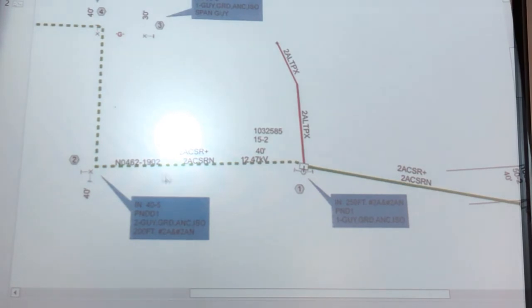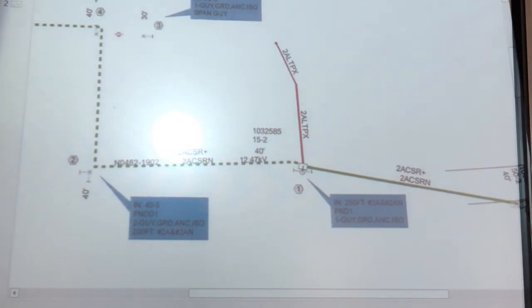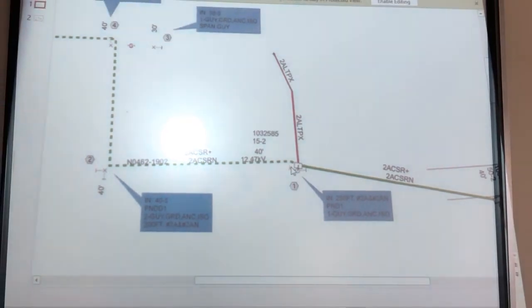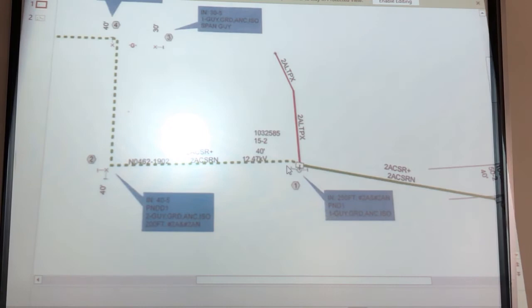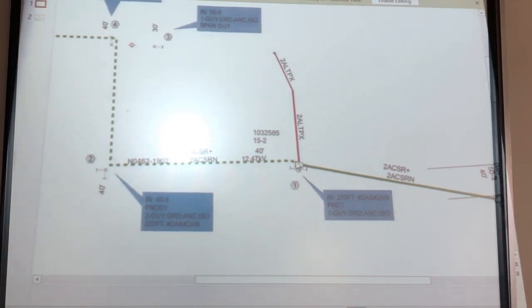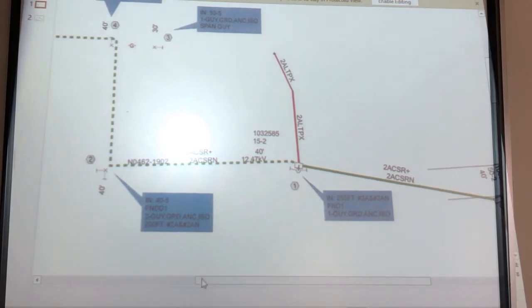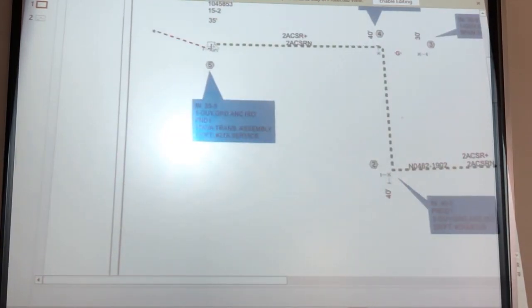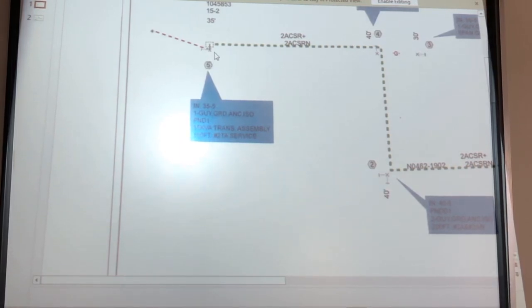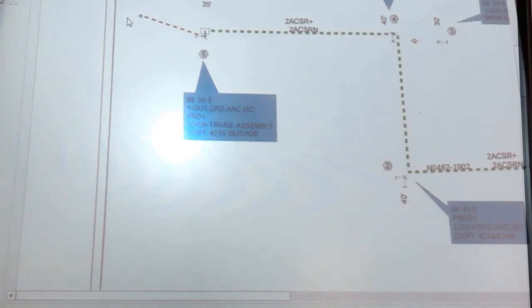So when you set up here, you're doing your cover up, and all you're gonna need to do here to safely pull this wire up, more than likely into the energized area, because all of this is existing, meaning it's energized. So you pull it up, dead it in, primary and neutral wire, and once you build your jumper to energize the new wire, someone will go back here to location 5 and energize that transformer, and that will energize the service for the house that's being built here.